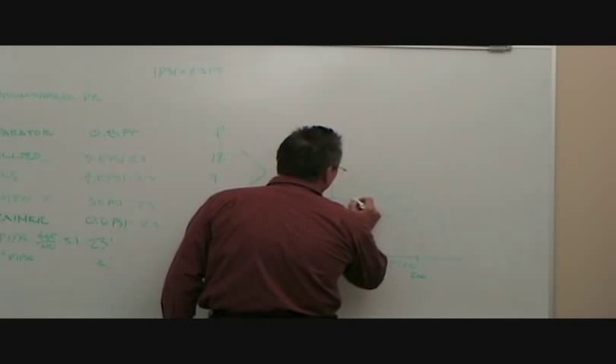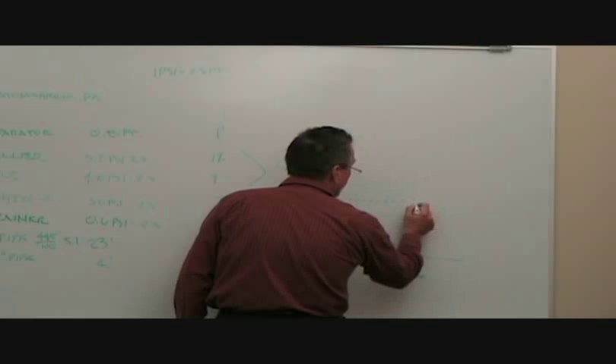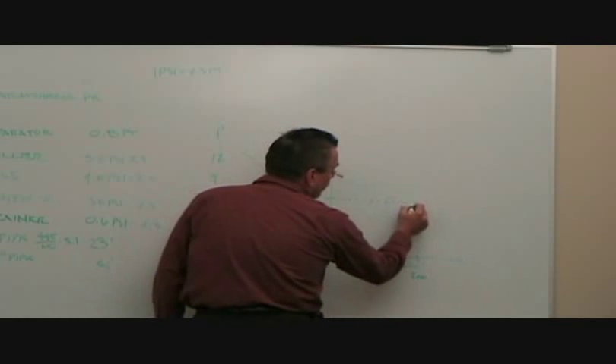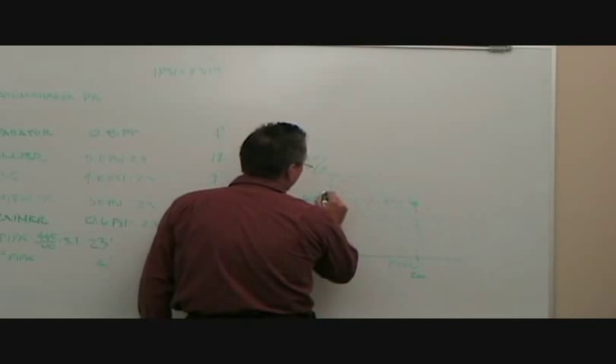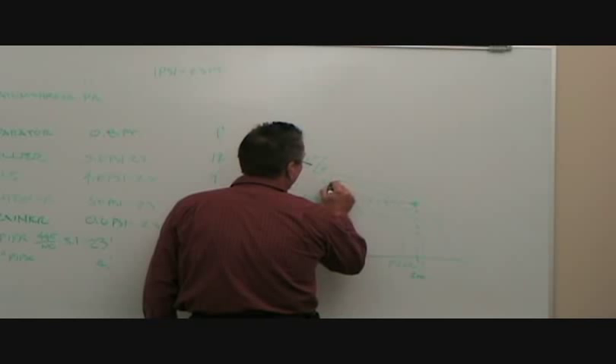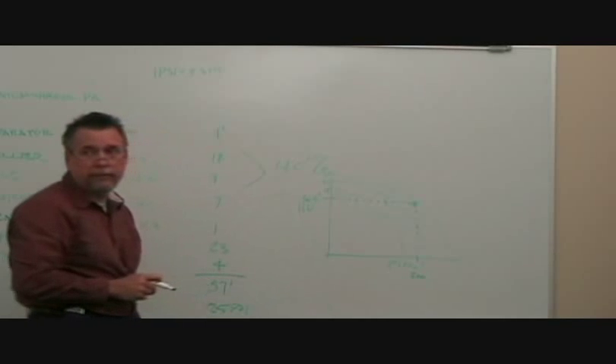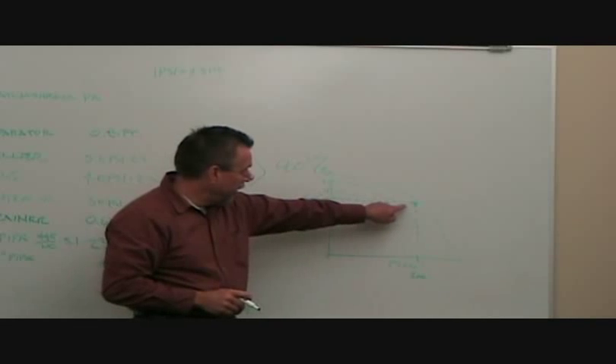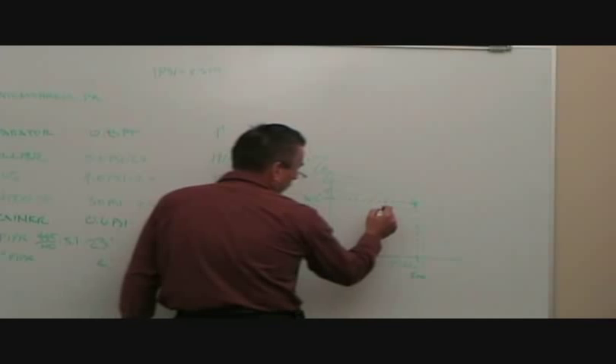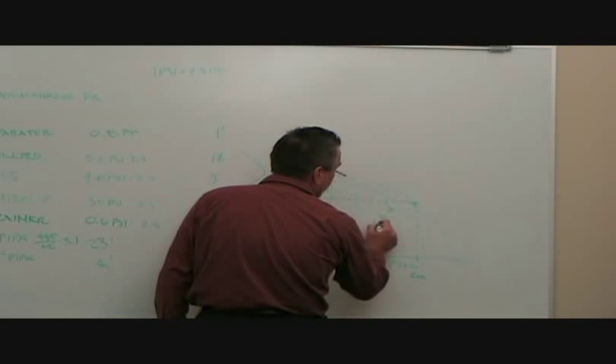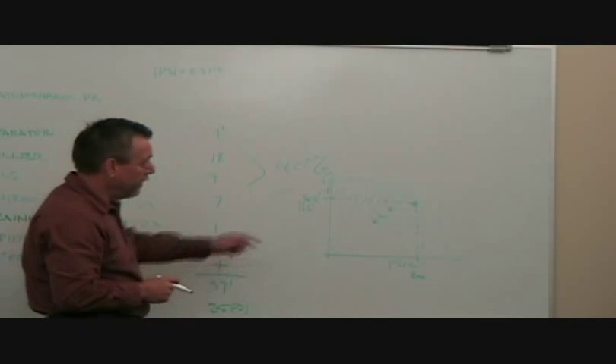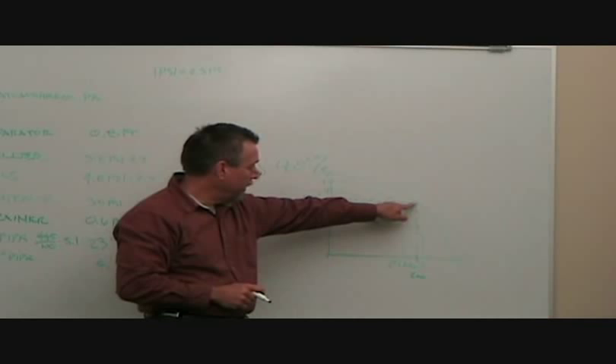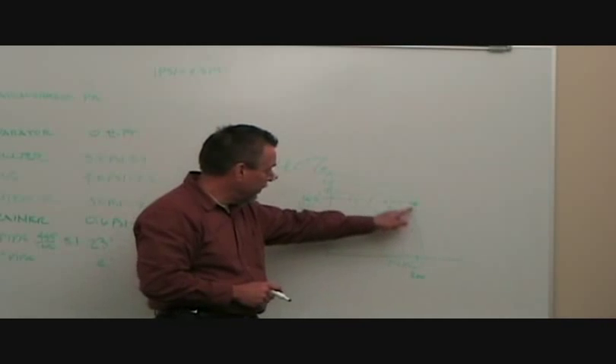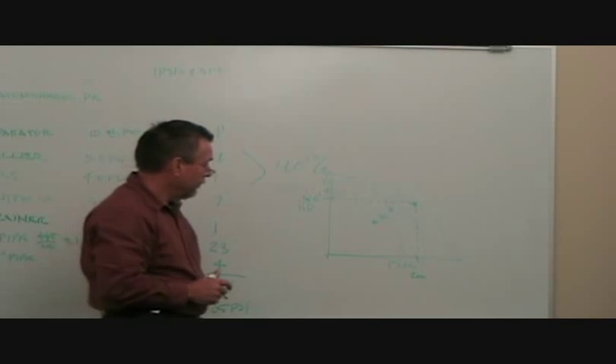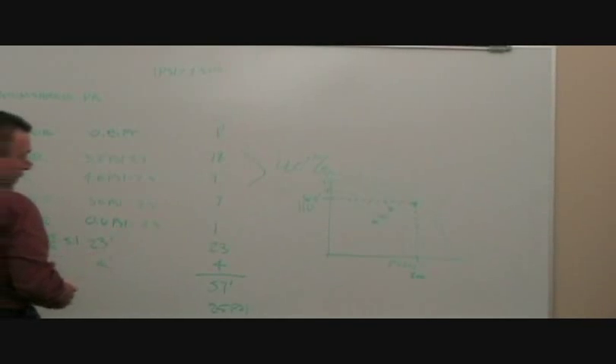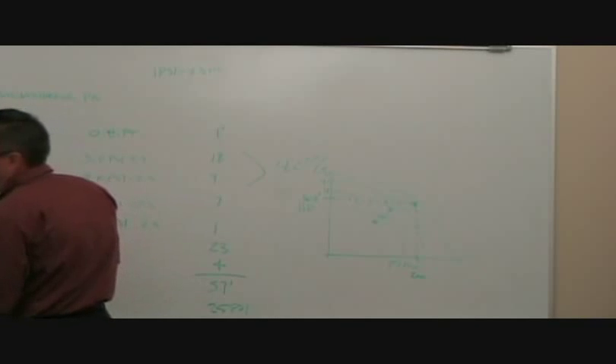So if I had this particular pump curve and I plotted these lines, it intersects right there. Let's say this is a 4-inch impeller, this is a 4.5-inch impeller, and that's a 5-inch impeller. And I'm right in the eye of the best efficiency. So this is something like 75 and 70 and 65% efficiency lines that show up on the curve. So I've got a pretty good selection here, right in the middle of the curve. If I had a pump curve, that's probably on something like a 2-inch pump.